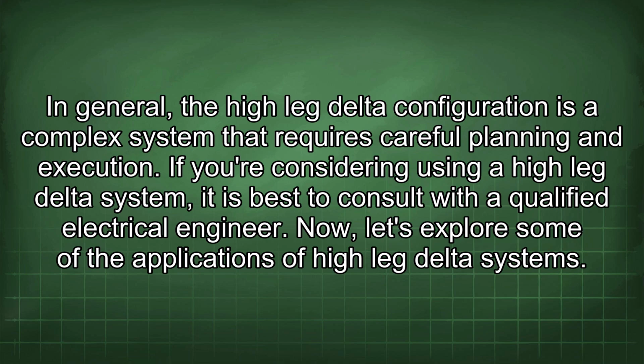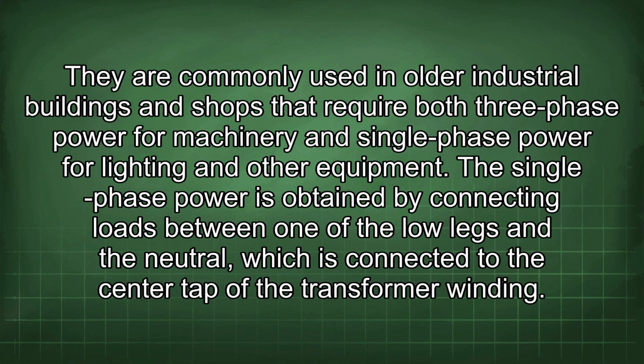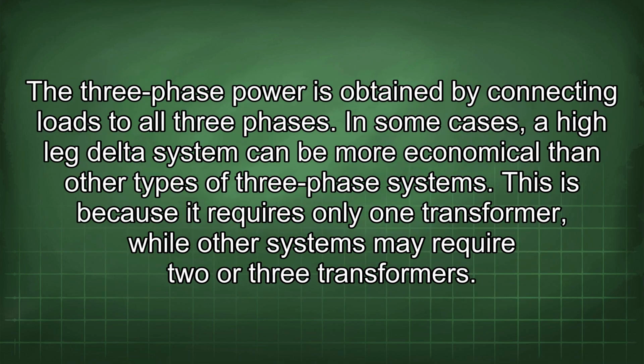Now let's explore some of the applications of high leg delta systems. They are commonly used in older industrial buildings and shops that require both three-phase power for machinery and single-phase power for lighting and other equipment. The single-phase power is obtained by connecting loads between one of the lower legs and the neutral, which is connected to the center tap of the transformer winding. The three-phase power is obtained by connecting loads to all three phases.